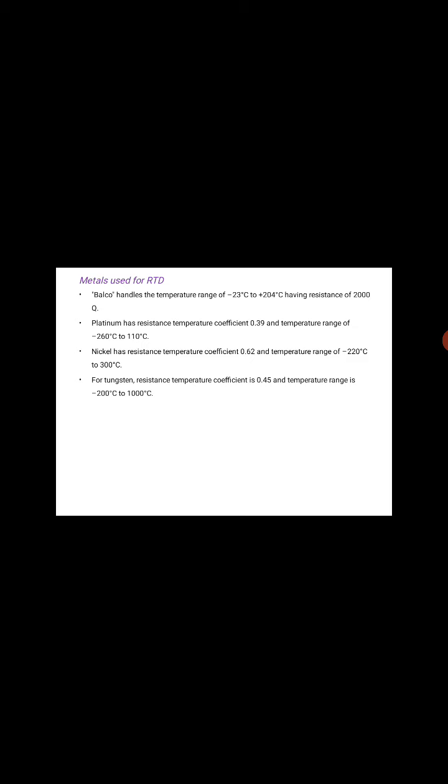Materials used for RTD: Balco handles the temperature range of minus 23°C to 204°C, having a resistance of 2000 Ω. Platinum has a resistance temperature coefficient of 0.39 and a temperature range of minus 260°C to 1100°C. Nickel has a resistance temperature coefficient of 0.62 and a temperature range of minus 220°C to 300°C. For tungsten, the resistance temperature coefficient is 0.45 and the temperature range is minus 200°C to 1000°C.